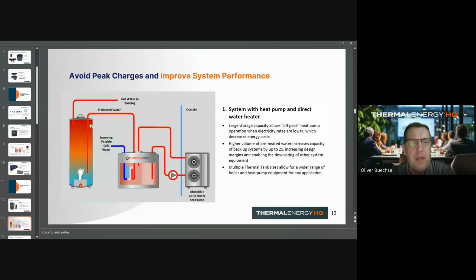All right. This is an example of how the tank and the heat pump work in conjunction with an existing system. Garth, can you give an example where such a setup makes sense, either from a legacy perspective or there is a need that does require that additional water boiler? Correct. If you've replaced your legacy system recently, you say, I've got a good natural gas hot water heating system in place, and I don't want to take it out of commission. Or if you have peak loads where you say, I need that fossil fuel device in order to meet some demands that happen within your consumption schedule.